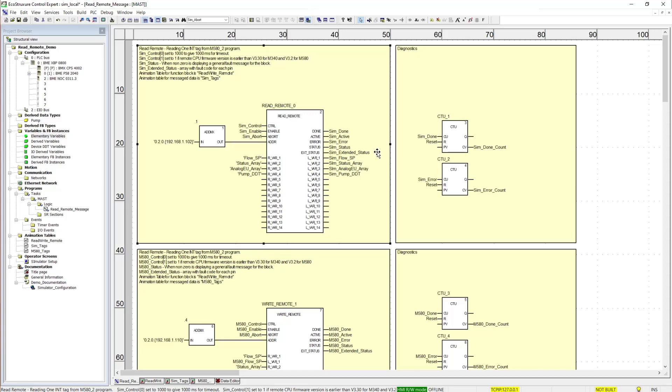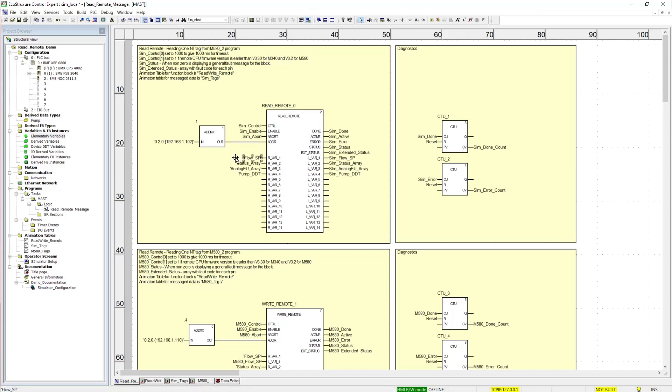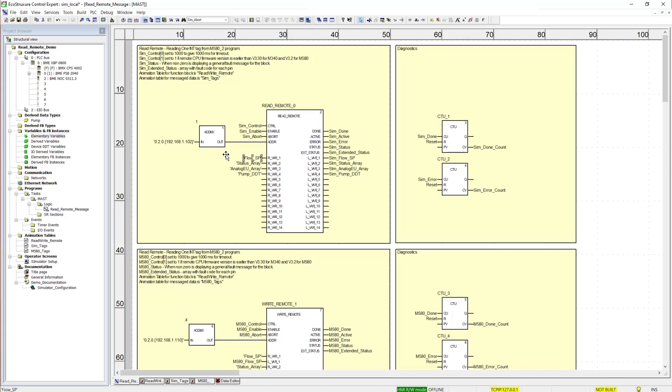So now we're down to the actual data transfer between the remote PLC and this PLC. In this case this is a read remote. So we are going to the remote PLC, finding a variable, and bringing it back to this PLC. On the left side we have the variable name in the remote PLC. This is a string format, it has to match what that name is in the remote PLC. And then on the right side we have the local variable. This is the variable we want the data put into. This variable data type has to match the variable data type we are reading from.